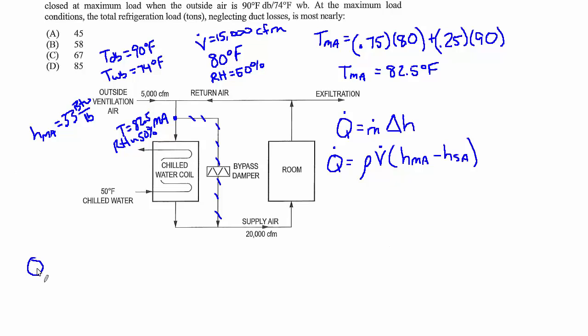Our ΔH is going to be H of the mixed air minus H of the supply air. Now we can begin to plug in. I'm going to come down here just so that I have a lot of room. I like to work out the specific volume from the density on the side sometimes just to simplify the substitution. So density is 1 over the specific volume. Also get the specific volume from the psychrometric chart. In this case I used the supply condition to look up the specific volume because it said the supply air is always 20,000 CFM. I suppose I could have used the mixed air—would have got a slightly different specific volume and therefore a slightly different density, but in all likelihood close enough for all intents and purposes. So in this case, 13.25 cubic feet per pound for the supply, and that works out to a density of about 0.075 pounds per cubic foot.